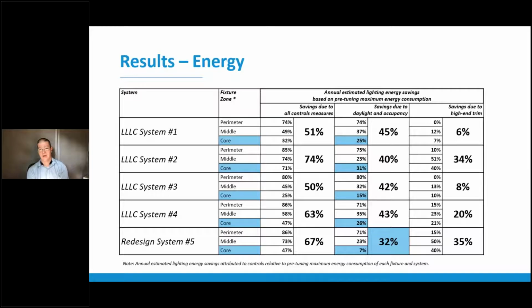And we're still working on trying to pull apart the occupancy data from the daylight data. All of this was coming from current transducers, and so it doesn't differentiate. So we're trying to use some smart overlays with weather data and occupancy patterns to pull those apart. But suffice it to say, a big piece of the difference is that we were not doing daylight harvesting in the redesigned solution for the core zone.